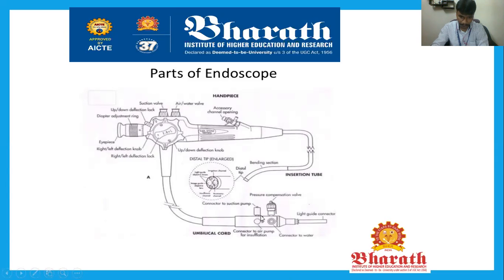It will also have a suction pump. Sometimes while we are inserting the endoscope, the patient may feel a vomiting sensation, or it may go against their body circulation or body movement. At that time some fluid can occur, which can make the camera blurry. To avoid that situation, the suction pump is used, and a pressure gauge is there to adjust the pressure inside the human body. An air pump and inflation connector are also there, which do not affect the inhale and exhale process of the human.